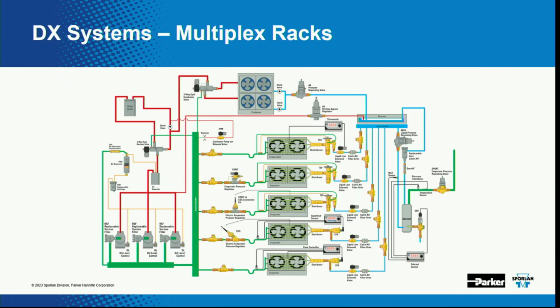Before we get into CO2, here is an abbreviated schematic of a supermarket rack, a multiplex DX rack. So DX, direct expansion, we're expanding the refrigerant. Just kind of going around the loop here, I'm going to start up here at the condensers. So coming out of the condensers, you've got liquid refrigerant.